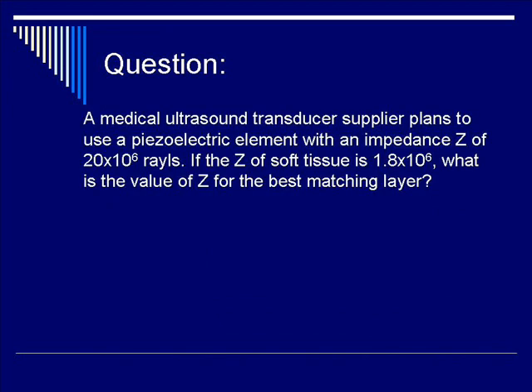Let's do a question to test your knowledge. A medical ultrasound transducer supplier plans to use a piezoelectric element with an impedance Z of 20×10⁶ rayls. If Z of soft tissue is 1.8×10⁶, what is the best value of Z for the matching layer?